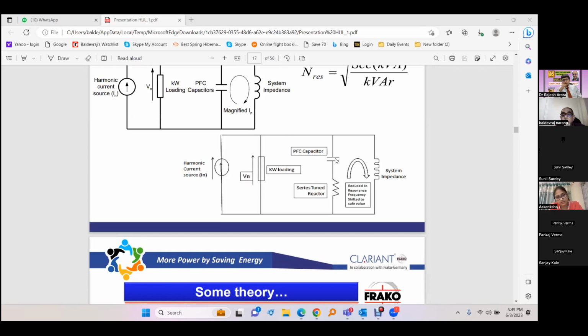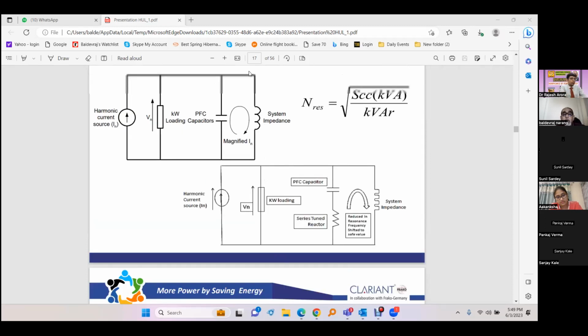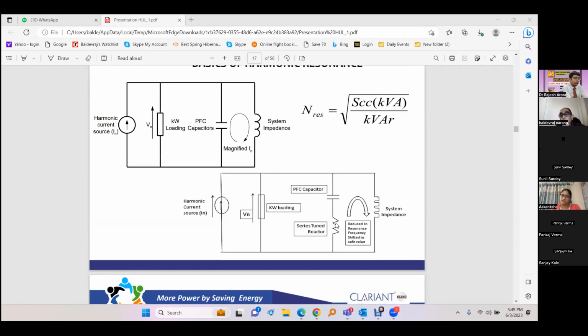with the capacitor. If we have only a capacitor, it is going to cause resonance, and the export of the harmonics will continue. So now we have the norms, and we have to maintain IEEE 519 norms. So this is a passive solution. By using the reactors, we can remove the harmonics.